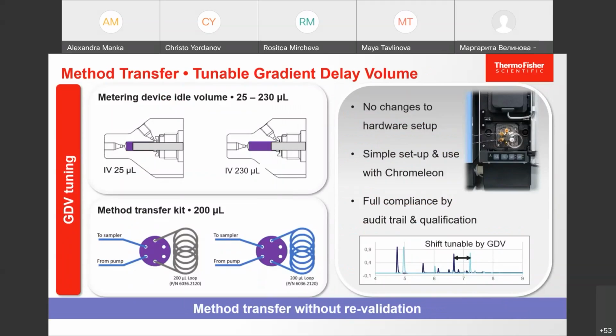In the auto sampler, we have a metering device that aspirates your sample. Basically, this is a piston that is movable, and you have a volume in here. In this metering device, you can set the volume between 25 and 230 microliter. So you have the option to play with 200 microliter of gradient delay volume in here.